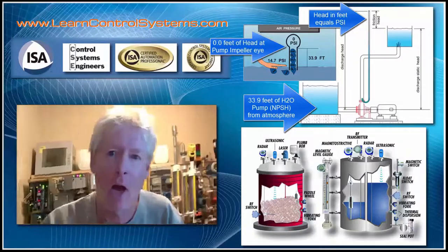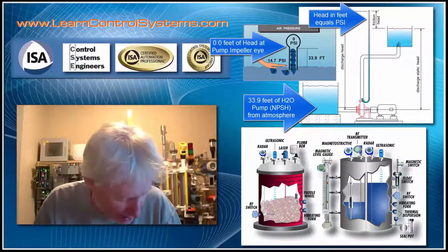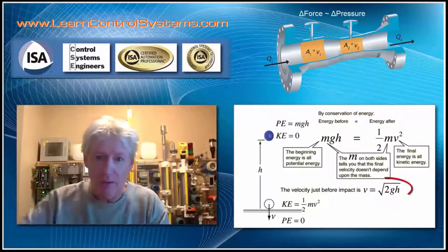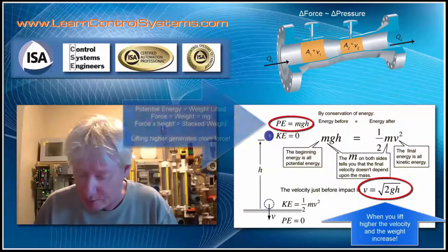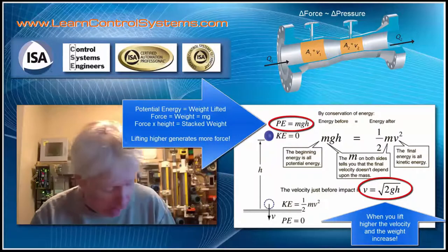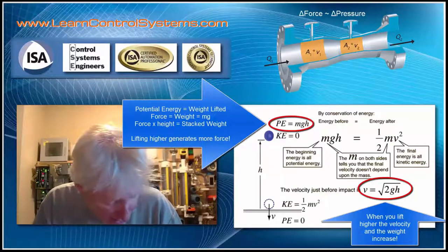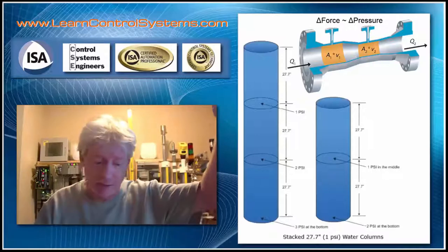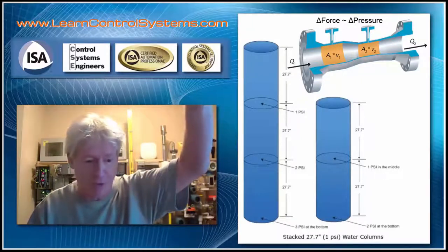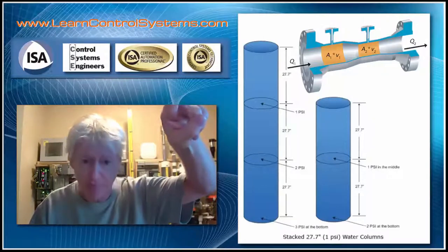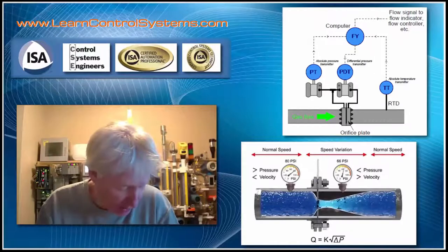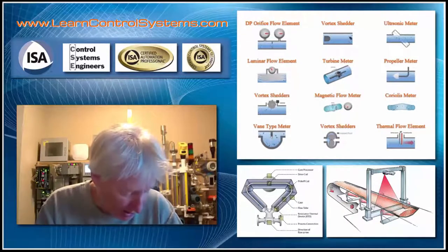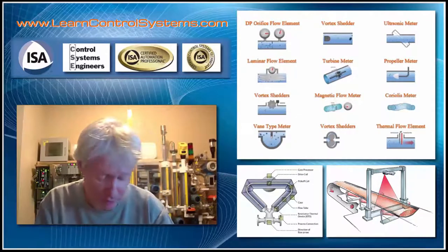Level measurement is based on head, work, and force — specifically how high a mass is relative to the earth. We raise something up to a level: it has potential energy, it falls down, the higher it is the faster it goes, and mass times acceleration equals force. This is how pumps work and how we measure levels in tanks. For flow measurement, we use the differential of height to give us a difference of force proportional to fall height. Velocity squared equals 2g times height. For mass flow, we can use gamma radiation to measure process density.